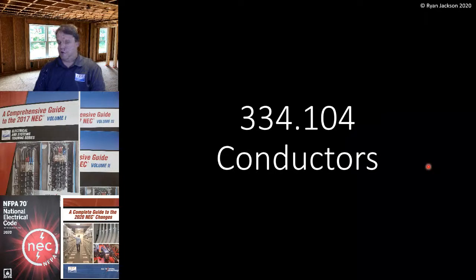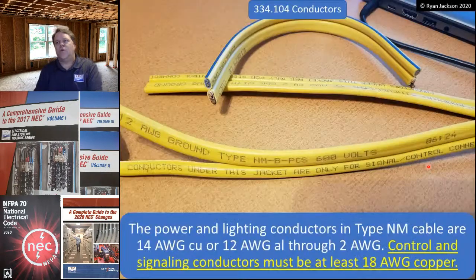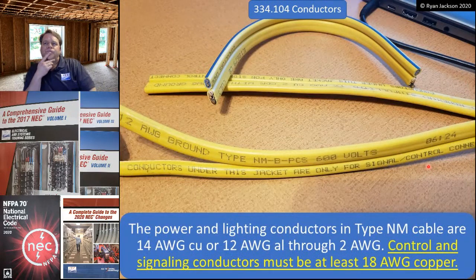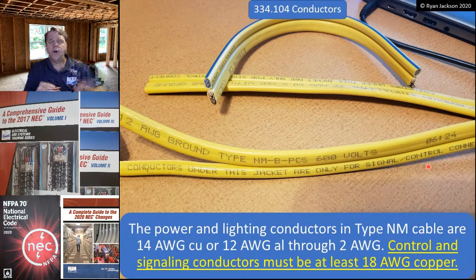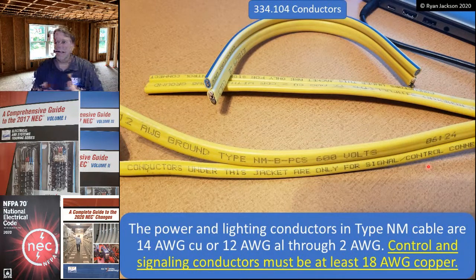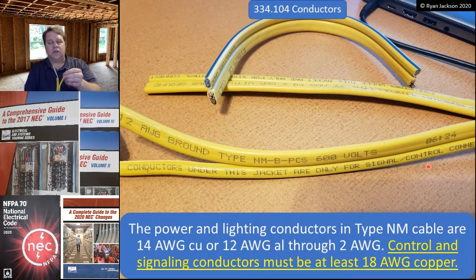Just about done. 334.104 is a section that I never really covered until the 2020 code because something kind of cool happened. The power and lighting conductors in type NM cable are size 14 gauge copper or 12 gauge aluminum all the way up through 2 gauge copper or 2 gauge aluminum. I never covered that because it was like, well, who cares? That's for the manufacturers and whatever. But in the 2020 code, we addressed this new really cool product, this twin cable or Siamese cable that you could use for lighting control.